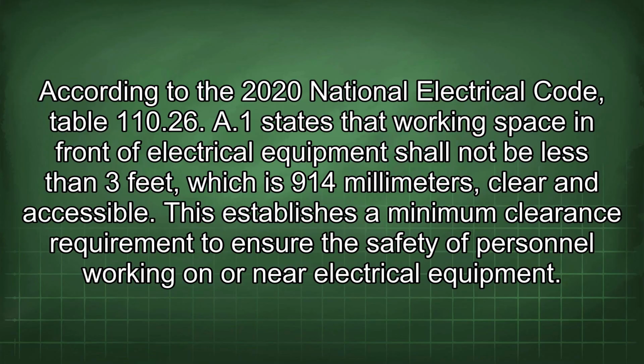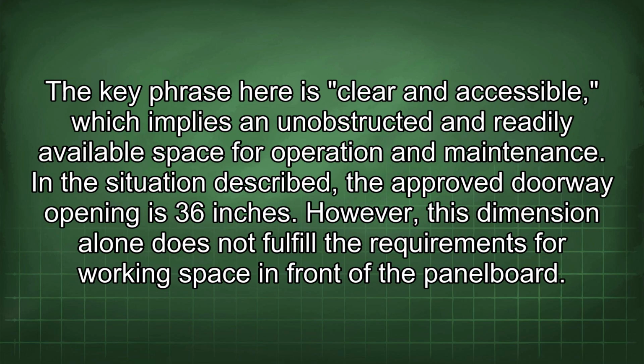According to the 2020 National Electrical Code, Table 110.26(A)(1) states that working space in front of electrical equipment shall not be less than 3 feet, which is 914 millimeters, clear and accessible. This establishes a minimum clearance requirement to ensure the safety of personnel working on or near electrical equipment. The key phrase here is clear and accessible, which implies an unobstructed and readily available space for operation and maintenance.